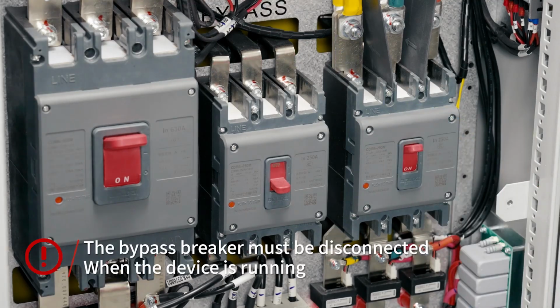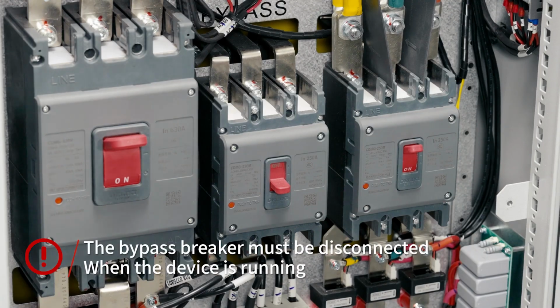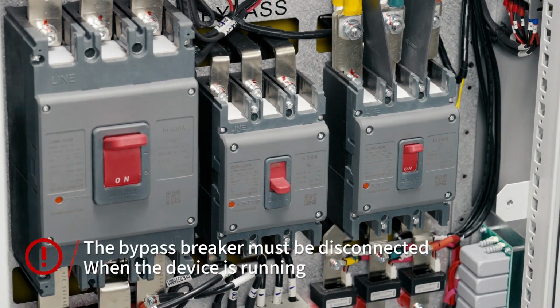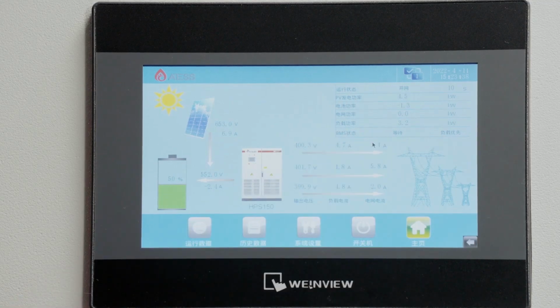The bypass breaker must be disconnected when the HPS is running, and it can be closed only when the system is faulty and the system needs grid or generator to run the load. Observe whether the output voltages of the 3 phases are stable and balanced. If not, please contact ATESS.